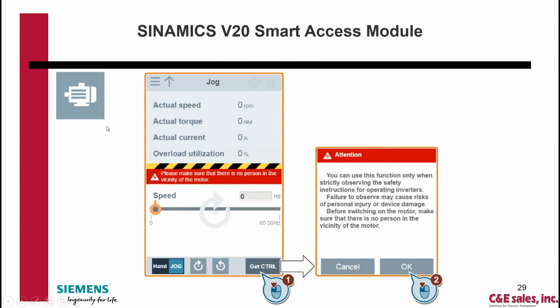Next, we'll look at jog, and basically this is what this jog screen looks like. You see it shows you what the actual speed, torque, current, and overload percentage is. At the bottom, you can see get control. So if you want the software to take control of the drive, you'll select get control. Then you've got options for jog mode. Jog is going to run it based on the icon selection, forward or reverse at 5 hertz. Or in hand, you can actually come and, in the slider, give it a preset or a speed command, and then there's a start-stop button that'll pop up on the screen at that point. And I'll show you that in a minute.